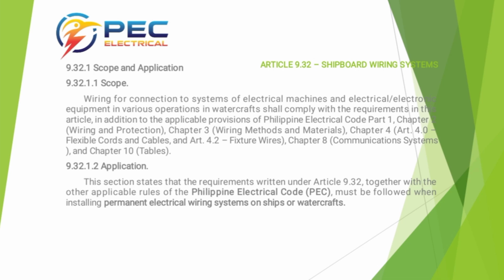9.32.1.2 Application. This section states that the requirements written under Article 9.32, together with the other applicable rules of the Philippine Electrical Code or PEC, must be followed when installing permanent electrical wiring systems on ships or watercrafts. So, any wiring used for electrical machines or equipment on ships or watercraft must follow the rules in Article 9.32 of the Philippine Electrical Code, along with other related PEC chapters. It states that these standards are required when installing permanent electrical wiring systems on any type of watercraft.